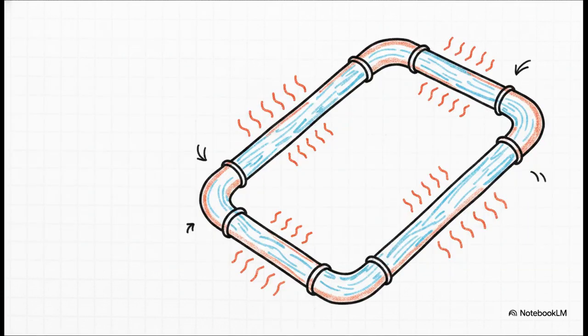But look, regardless of the production route you choose, whether you're using a traditional still or a cutting-edge membrane system, the engineering reality on the ground remains exactly the same. All WFI systems absolutely must feature sanitary design. They've got to be continuously circulated to prevent any stagnation, dead legs must be aggressively minimized, and the whole system has to be self-draining. On top of that, these systems are typically held hot or otherwise rigorously controlled to fiercely limit microbial growth. And obviously, they must be capable of being sanitized or sterilized in place.